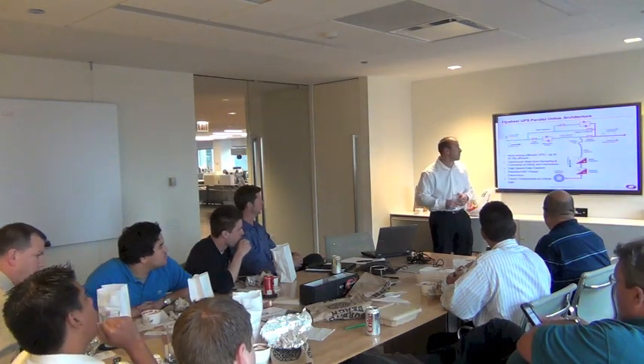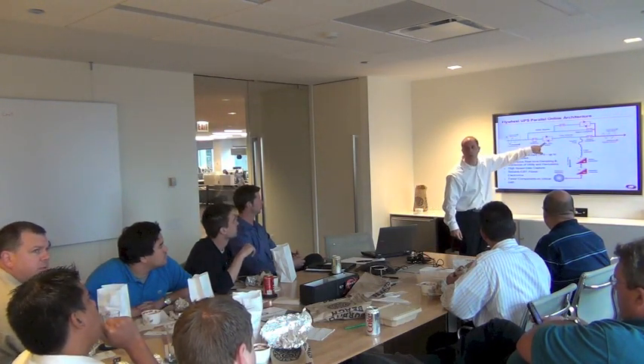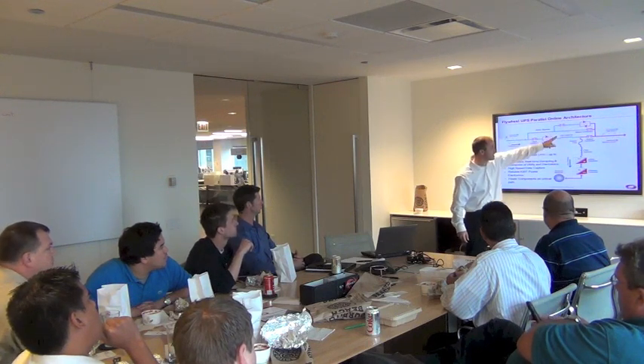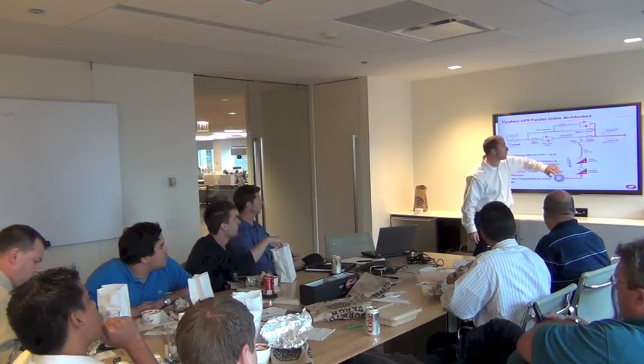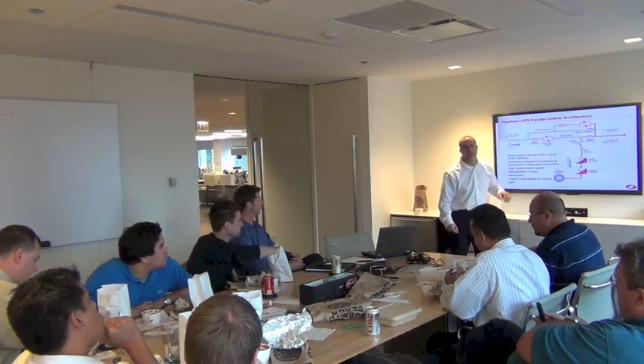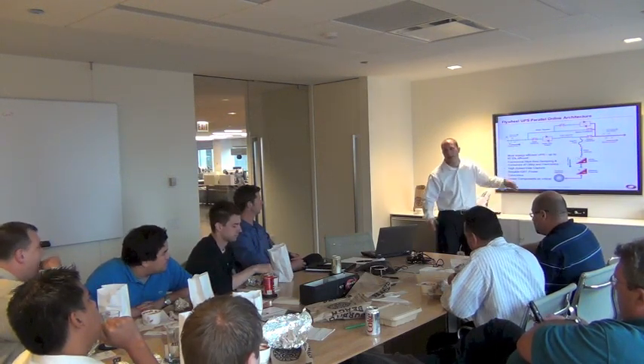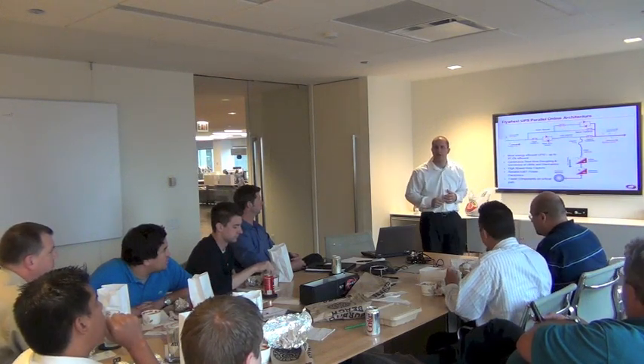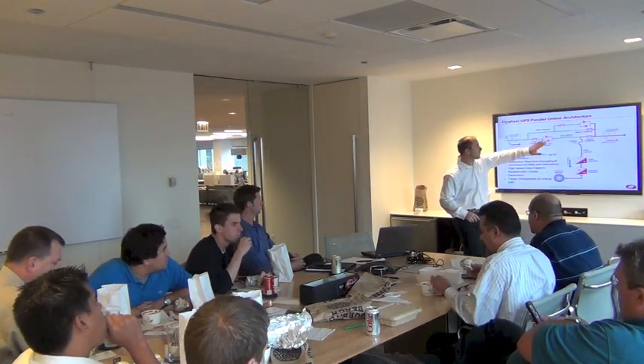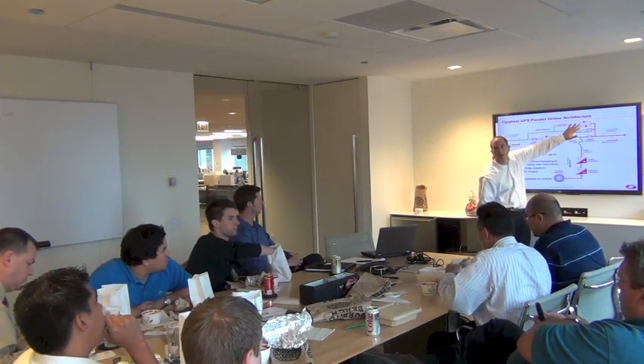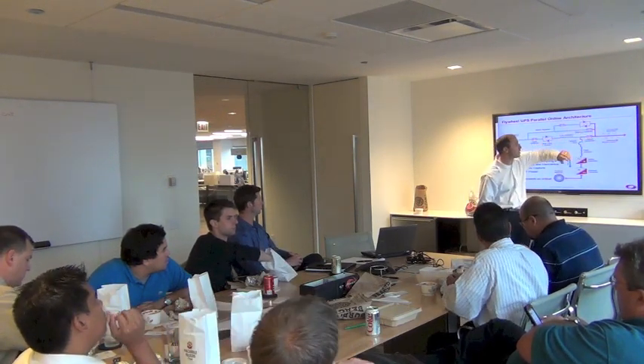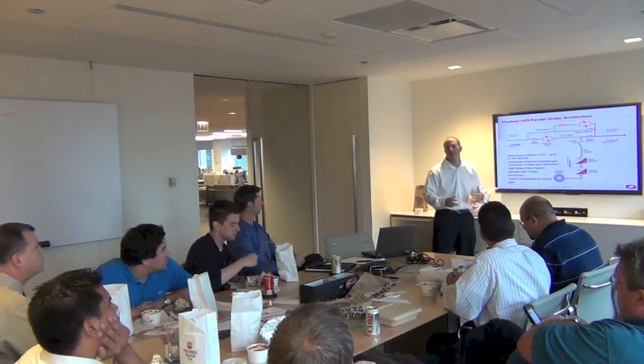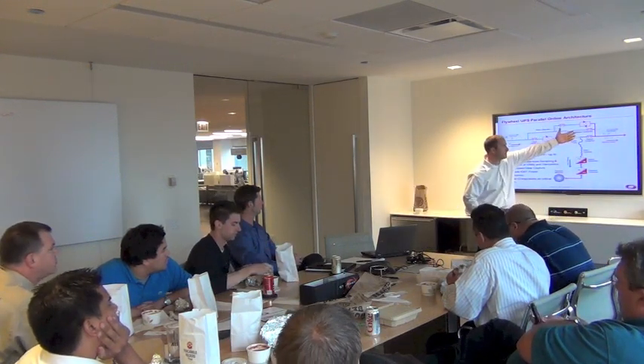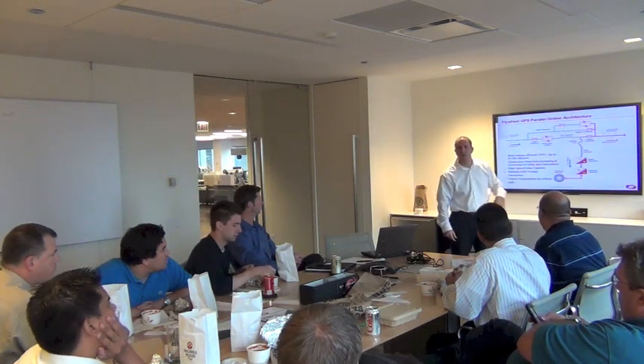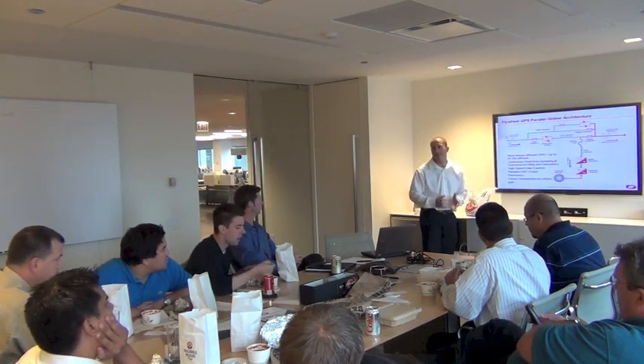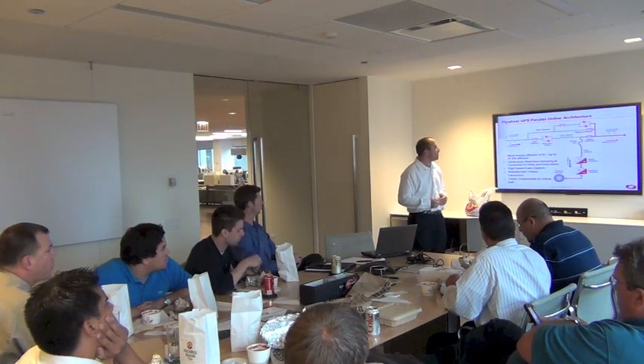So in other words, if you had a 900 kVA UPS, every one of these, input contactor, 100% continuous duty SCR-based static switch, line inductor, both your IGBT-based power converters, your flywheel energy, output contactor is in each flywheel cabinet, and so are the brains. So basically, each flywheel cabinet has its own brains. The way to really think about it is a bunch of 300 kVA UPSs in parallel. We also have a momentary SCR-based static switch on our bypass used in conjunction with a contactor or a breaker, depending on the size of the unit or the frame. For the single module system, it's 400 amps. For the multi-module system, the bypass is rated for 1600 amps because it's expandable out to 1200 kVA.